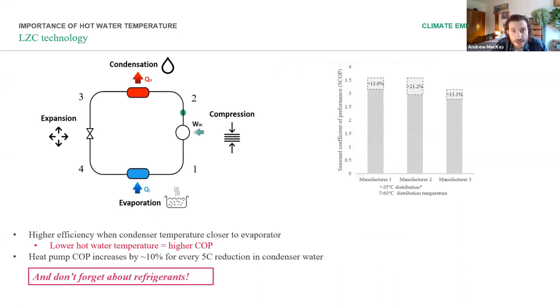I mentioned earlier that the hot water temperature actually affects the technology that we can use. And in a net zero economy, we need to be generating heating from electricity, not from gas anymore. So we need to be looking at heat pumps. And with heat pumps, the bigger the temperature difference between the water that we put in and the water that we take out, the harder the compressor in that heat pump has to work. So more electrical energy in means more energy consumption. So the lower we can bring that temperature down, the less hard the heat pump has to work.